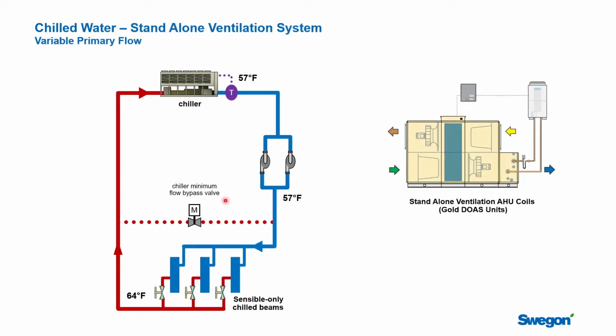Now, another way to look at chiller plants, and this might be more attractive on a smaller chill beam system, is that you dedicate a loop to the chillers. You dedicate the chillers to just the chill beams, and you separate your ventilation units and make them standalone. So most likely some form of integrated DX. And that does a couple of things for you. It allows you to simplify your chilled water system significantly. It's only going to be a 57-degree loop. You're going to get fantastic efficiency in your chillers. That's going to be very nice.